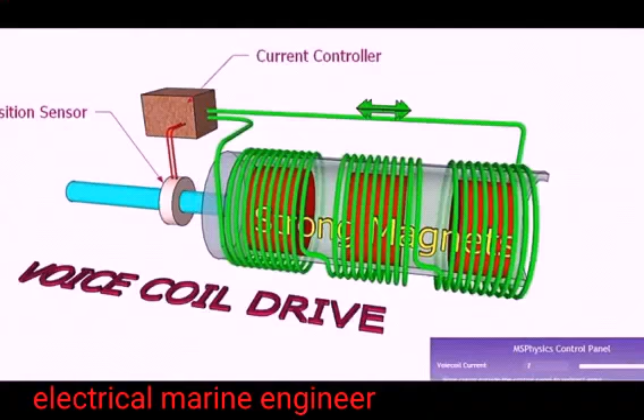And now we will discuss the voice coil drive. This is the setup of the voice coil drive, having permanent strong magnets stationary inside the coil drive, and the coil is a movable coil. It is in series for getting more power, and the current controller will give the proportional current, so depending on the current, the amount of movement will vary. That is achieved by the proportional controller of the FIVA valve. It also has a position sensor, which will give the feedback of how much the valve has moved. And this is the voice coil drive mechanism.